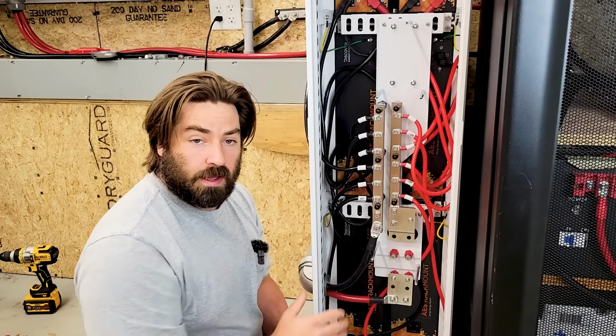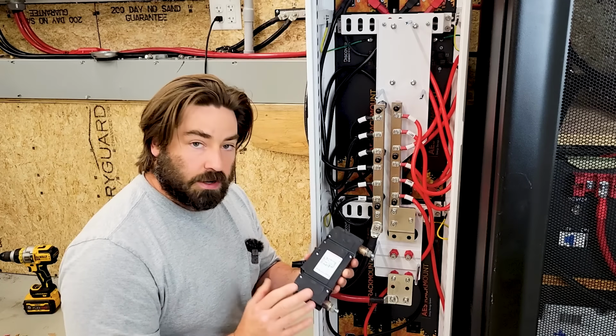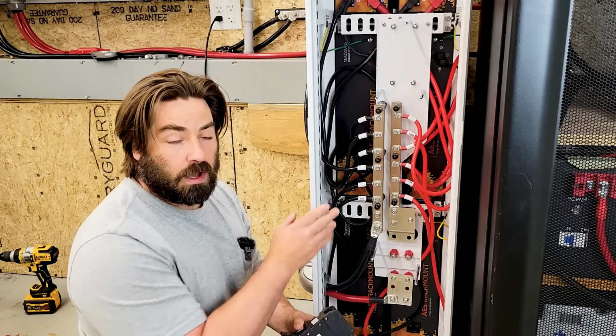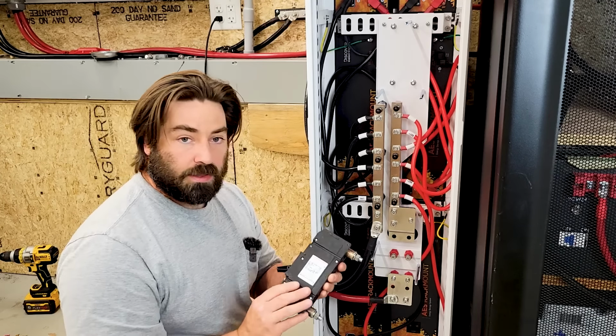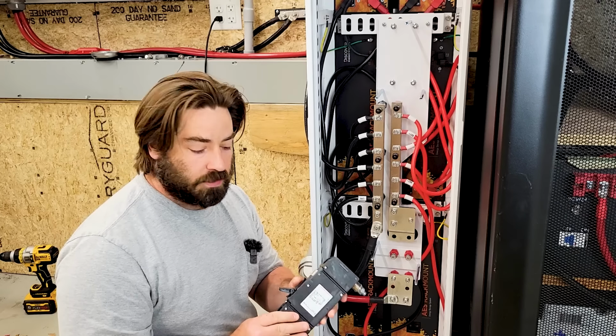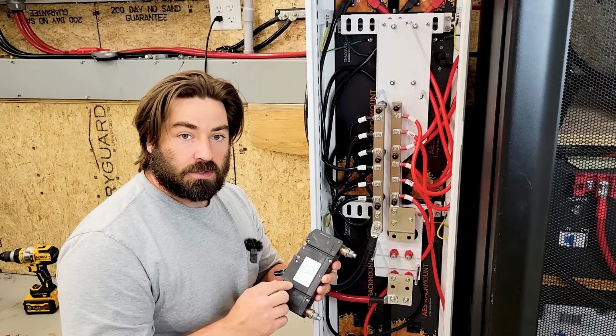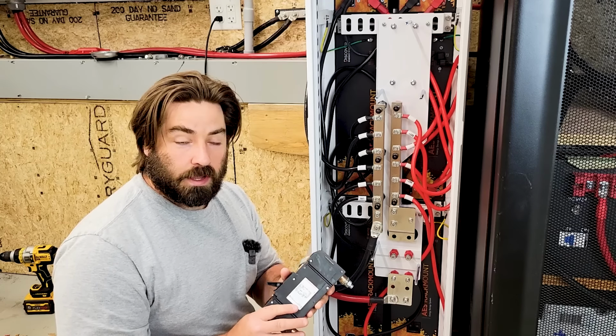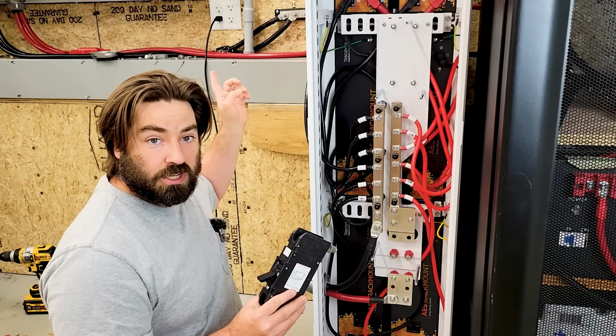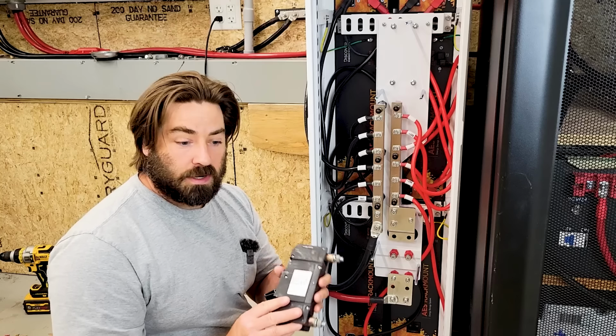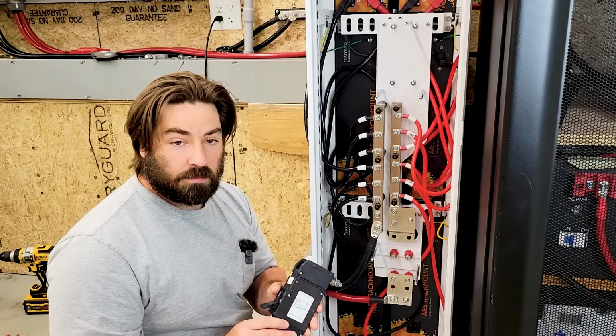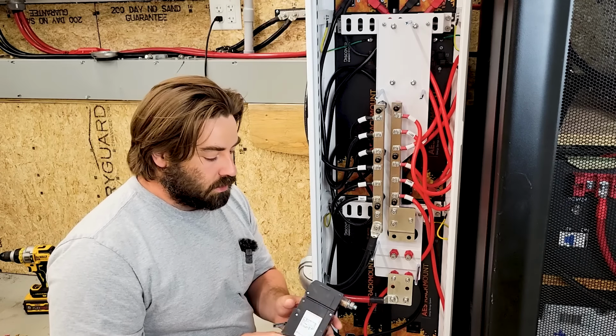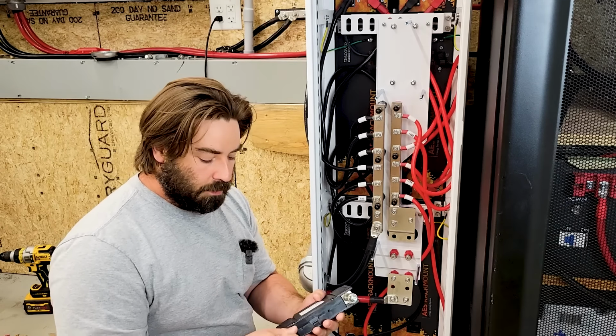With all the wires torqued down, it's time for the circuit breakers. These are a separate part number, they don't come with the cabinet. These are 250 amp circuit breakers, 125 volts DC. Really nice, big, beefy circuit breakers. I've seen these same circuit breakers used in a bunch of other applications, like the Schneider PDP and some MidNite Solar DC disconnect boxes. So they're very popular, very good quality circuit breakers.